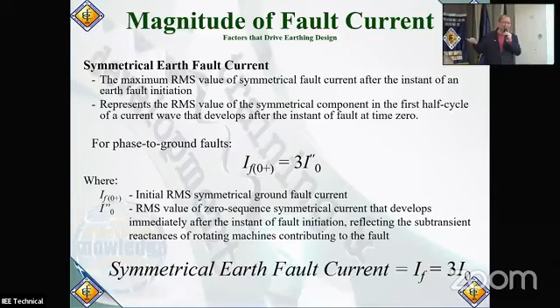There's always that approximate value. What is the maximum earth fault current that will be present in a system? And a maximum fault, what they call an ideal line to ground fault with maximum offset, is always equal to your 3-phase fault current. Pareho yan. The maximum theoretical line to ground fault is always equal, in fact sometimes more than your 3-phase fault. So that's why, kung hindi mo alam, just use your 3-phase fault current as a calculational basis. Kaya nga sabi ko dito, yung symmetrical earth fault current is equal to your symmetrical fault current, 3I0. It's a long process of calculation in the symmetrical components. When you have a maximum offset perfect fault, one of the phase voltages equals the phase-to-phase voltage. So yun, maximum offset, maximum fault current na rin ang lumalabas nun. So kung gagamitin mo yan, you're probably safer than you should be.